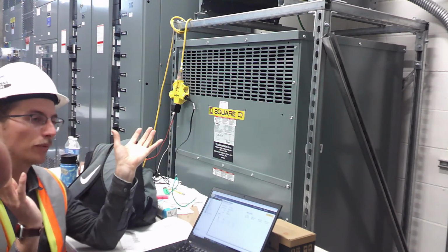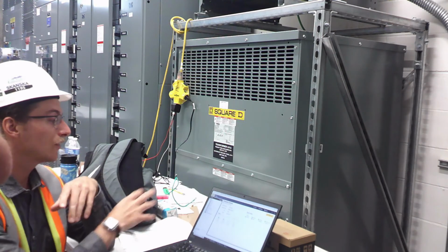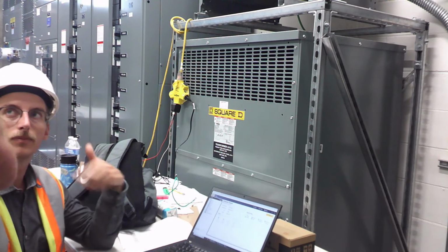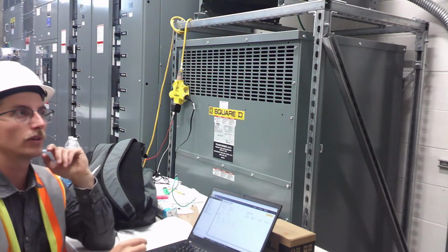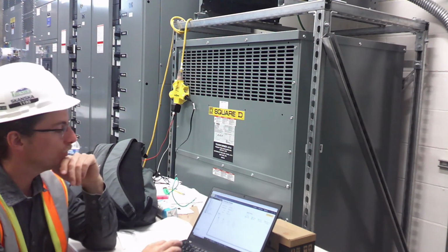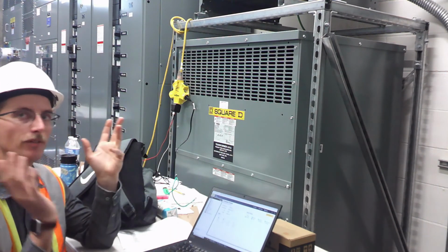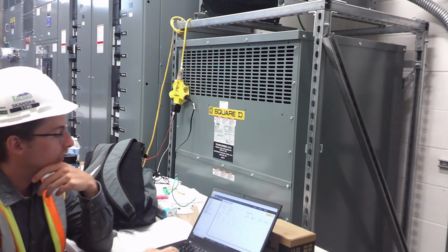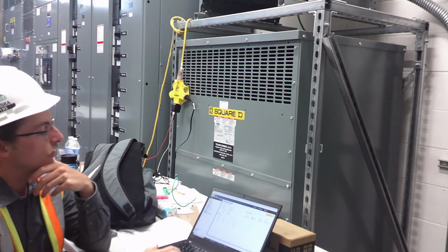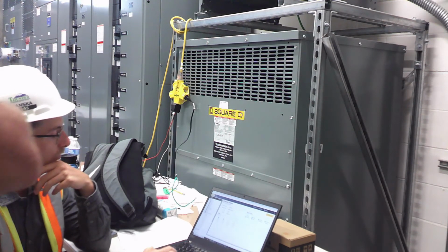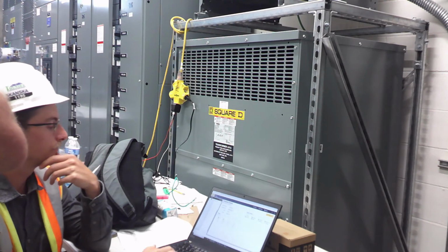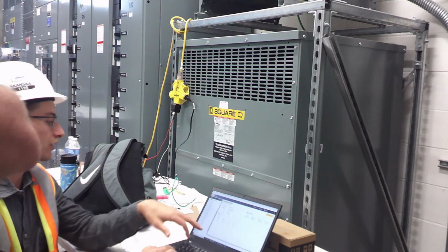It's such a big network that even if you don't add any new devices, it'll take like 20 minutes for it to go through and scan the entire building, which is very dependent on how many devices you have in the network. You'll see those pop up down here in your uncommissioned devices. So expand this. This has got all the relay panels. It keeps those in there just as a container.